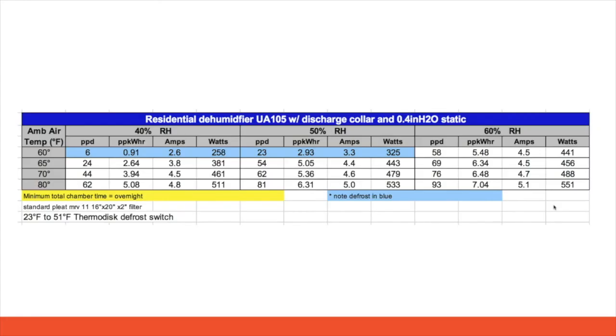So here is a performance curve. This was our UA105 dehumidifier, and this is at 0.4 water columns of static. And you can see at 80 degrees on the left-hand side over the 60% RH, when we add the static pressure, that reduces the dehumidification output of that dehumidifier.